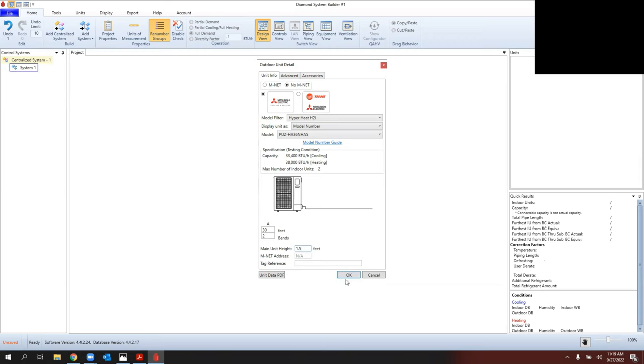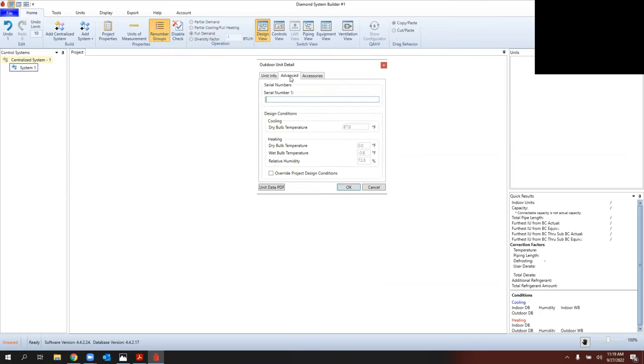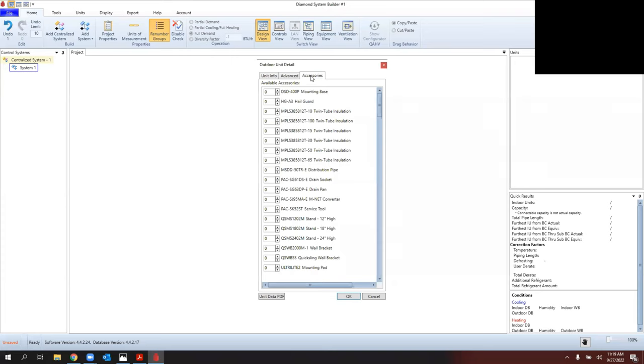Let's say the condenser is 1.5 feet off the ground. Negative numbers apply to indoor units if they're below the condenser — for example, if the condenser is on a roof and you go down several floors, that could be minus 20. The system keeps track of and de-rates each indoor zone based on elevation, line set length, and operating conditions. Under Advanced, you can override project design conditions for a condenser designed for different operating conditions, and it lists every accessory in the Mitsubishi catalog.